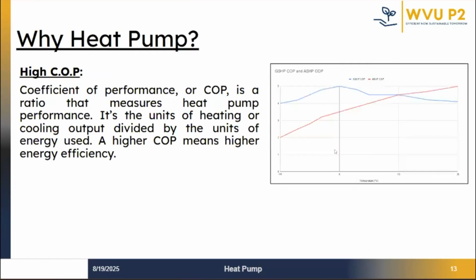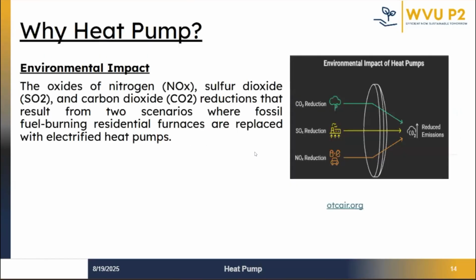So heat pumps are also efficient because of their higher coefficient of performance. They deliver multiple units of heating or cooling for each unit of electricity. The chart shows that ground source heat pumps keep a stable, high COP since ground temperature stays fairly constant. Air source heat pumps may vary more because outdoor temperatures change. When it's cooler outside, the heat pumps must work harder and the COP may drop. In short, stable source temperatures mean higher, steadier efficiency. COP values of heat pumps typically range around 3 to 4, which is highly efficient for a heat pump.